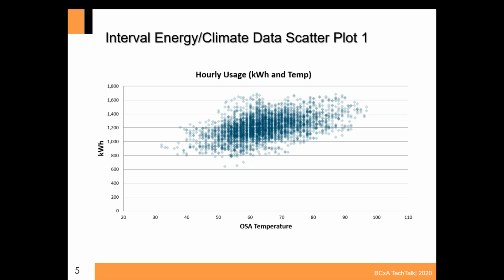There is a significant variation in magnitude of consumption, regardless of outside air temperature. So I think what I'm getting from NDEEP is there's a high base load. And what I'm not seeing is anybody talking about the 3rd observation, which is really hard to make. Let's recap the 2: energy goes up as outside air temperature increases, and we have a high base load. If you can see the mouse on the screen, the energy use is always about half of the peak, which is pretty significant. But the 3rd observation I'm going to hold on.